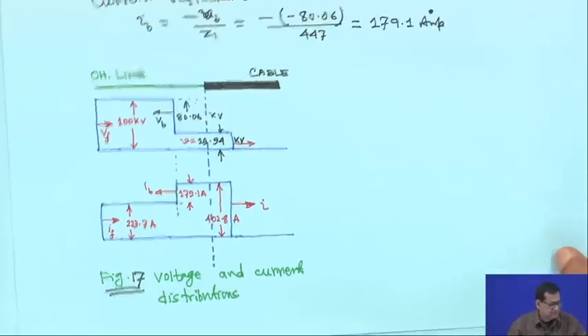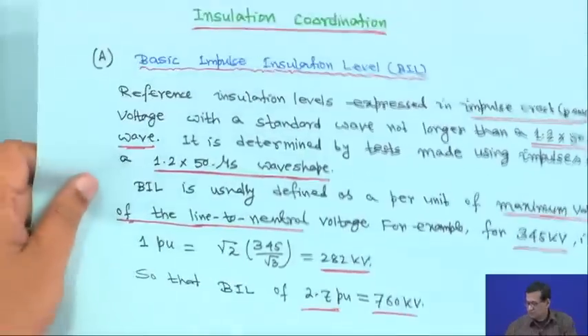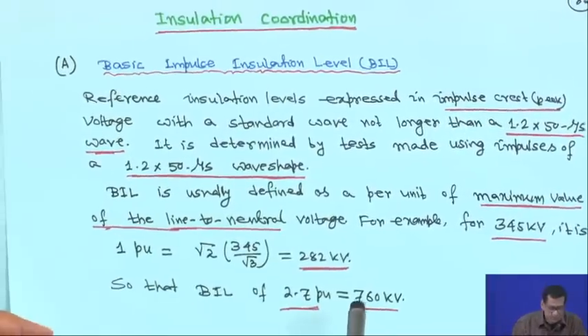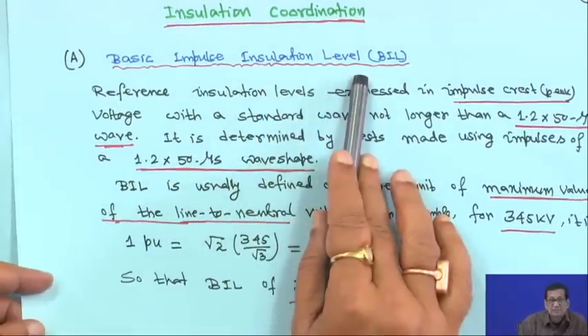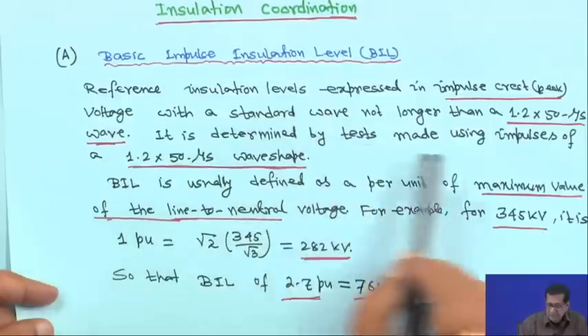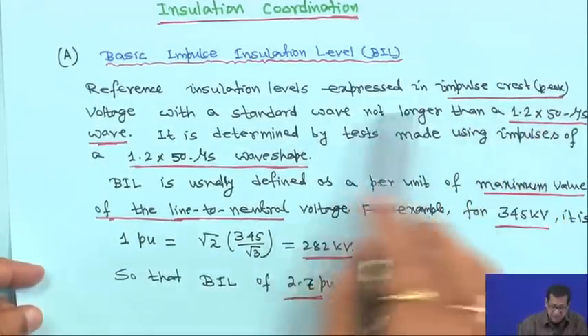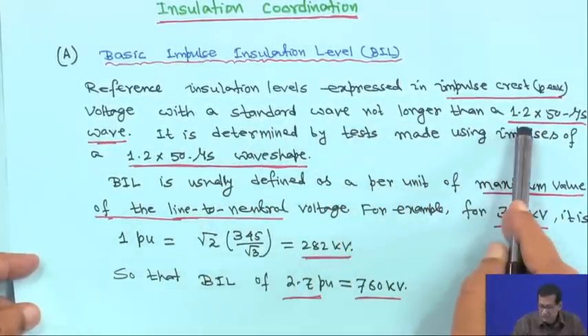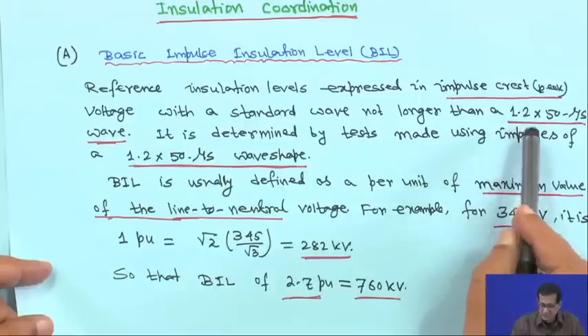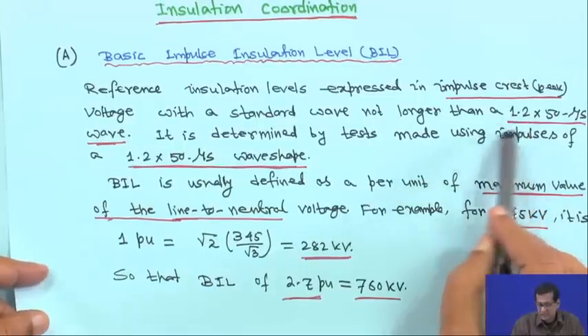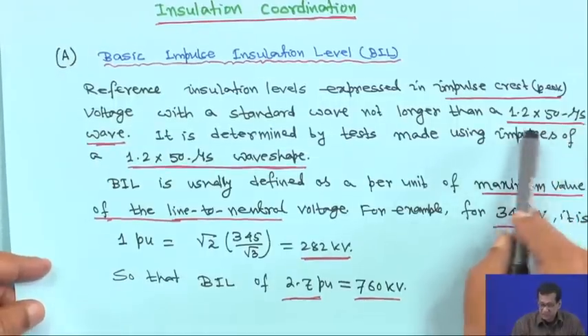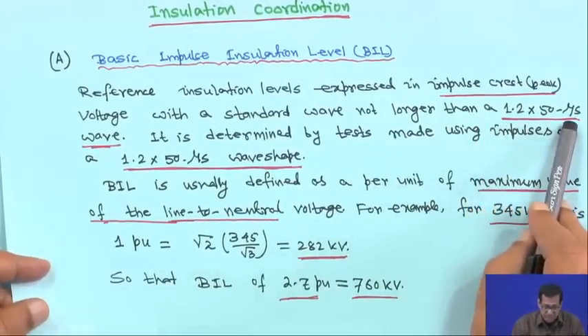Once this transient overvoltage discussion is over, we move to insulation coordination. First, the Basic Impulse Insulation Level, or BIL: it is the reference insulation level expressed in impulse crest — that is, the peak voltage — with a standard wave not longer than 1.2×50 microseconds.